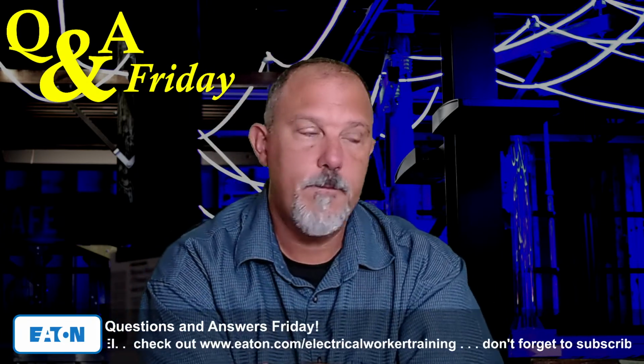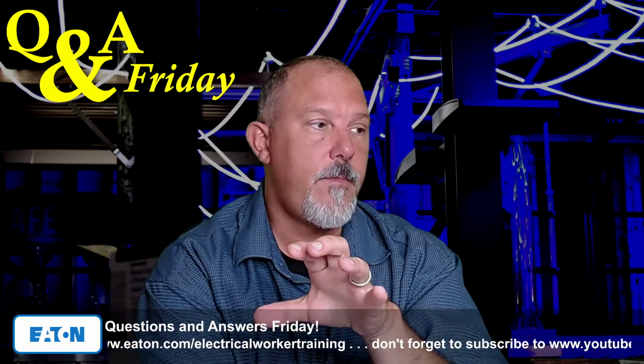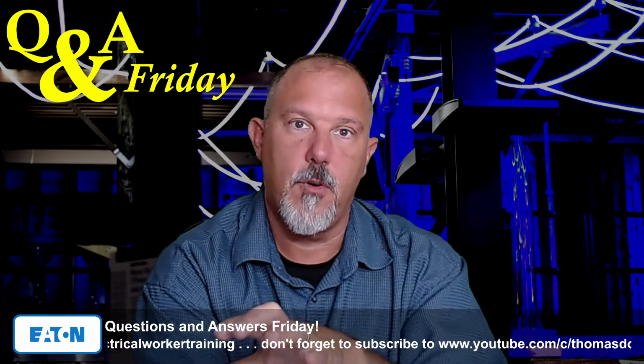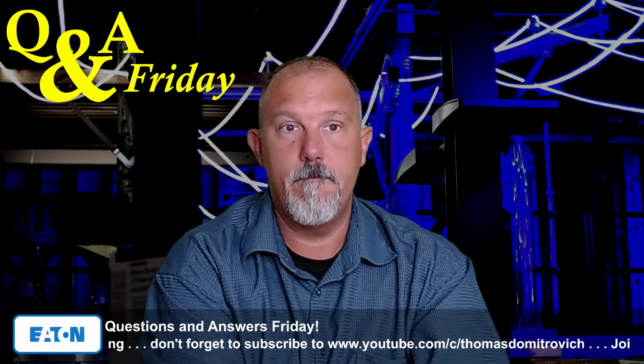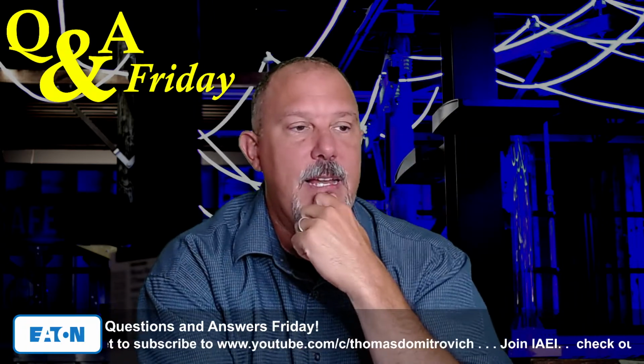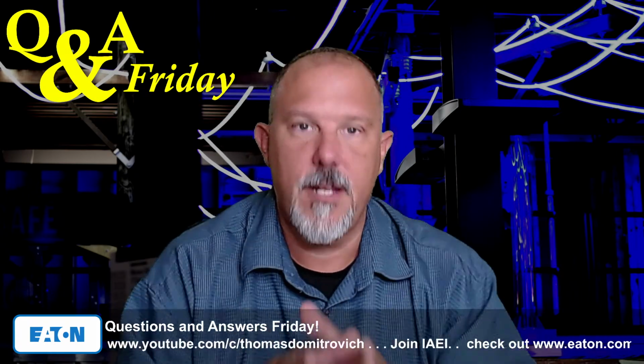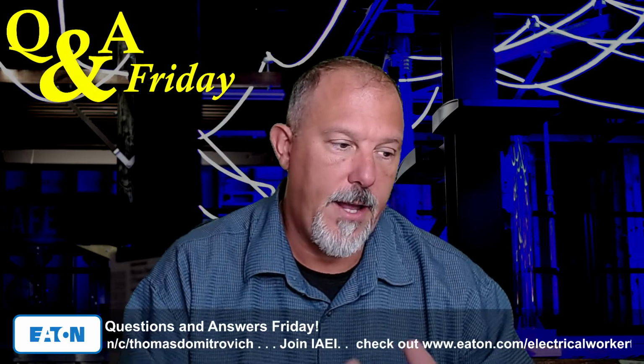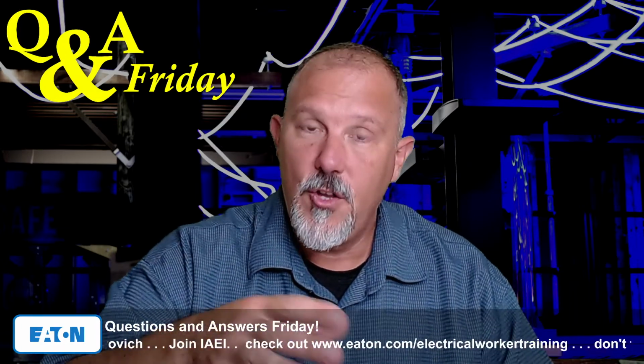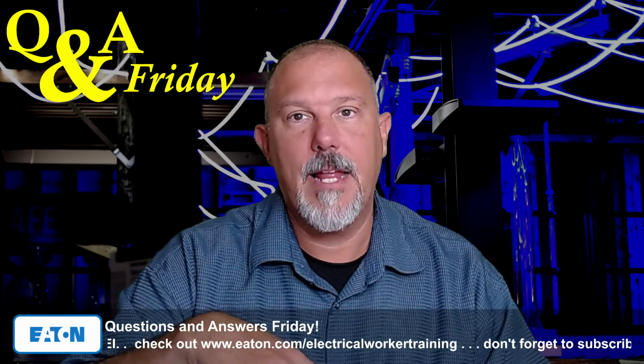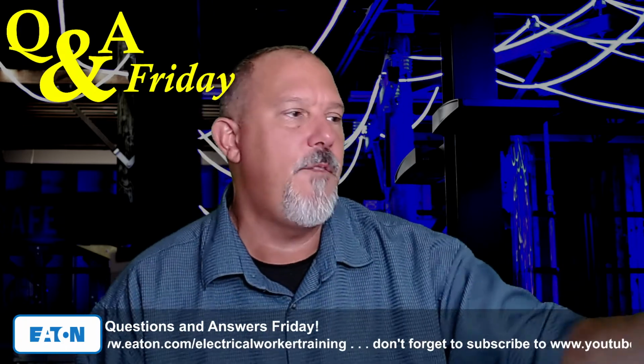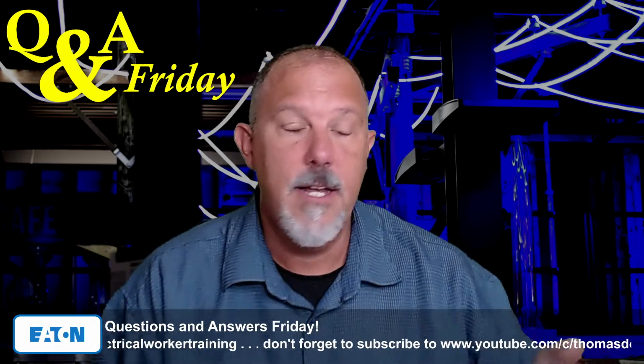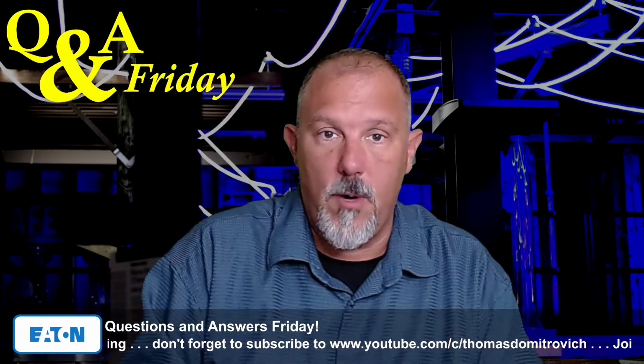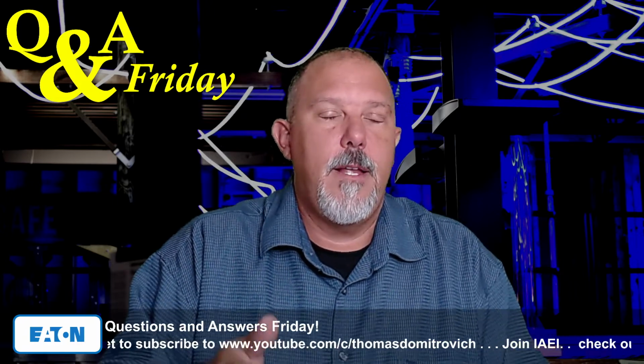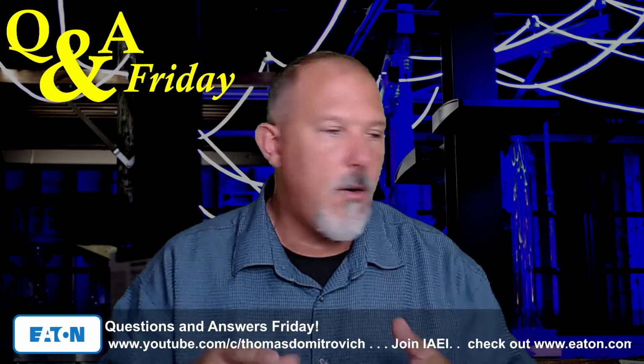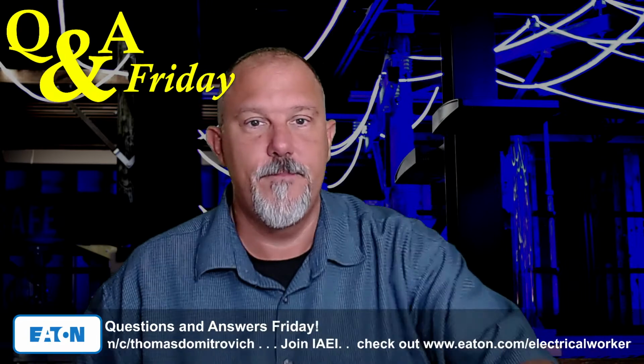It has an impedance, and we know what the impedance is. If you look at my infinite bus video, I will try to put a link to that up above. The infinite bus video goes through the calculation, because to understand an infinite bus, you have to understand the impedance diagram. And the fact that my source, that 5,000 MVA short circuit available fault current from the utility that you're talking about, on the line side of a 1-to-1 transformer, is a very small impedance. So if I draw, we're going to try this again.